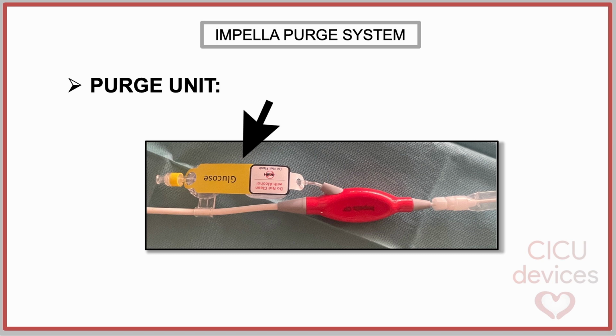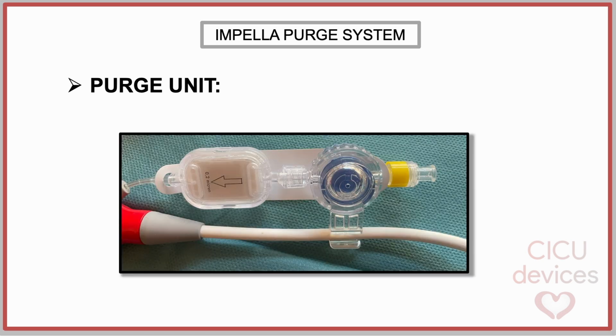The Impella CP purge unit comprises an integrated filter reservoir check valve assembly. It was redesigned as a single, unified component to minimize the risk of tubing kinking, disconnection, or structural fracture within the purge system. This integrated design improves mechanical stability and enhances overall system reliability during clinical use.